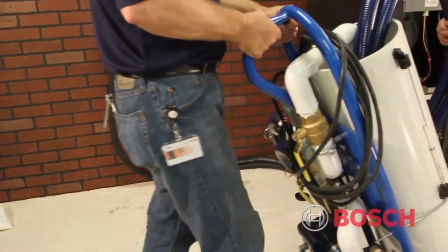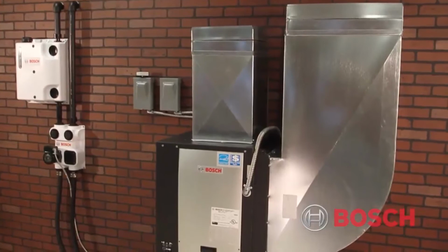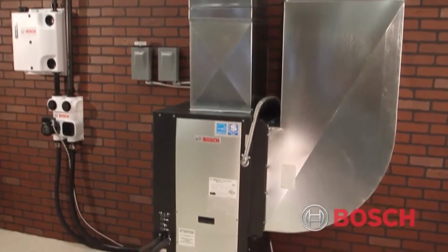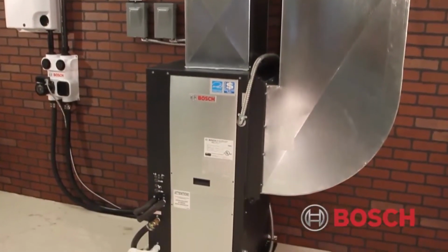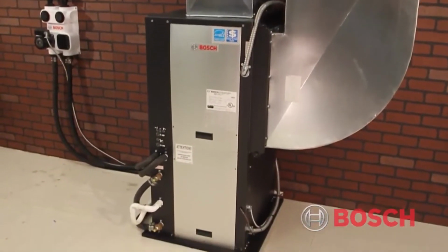The GeoLoop is now completely flushed of air and debris, and the unit is now ready for startup commissioning. It's recommended at this point to remove and clean the flush cart screen filter.